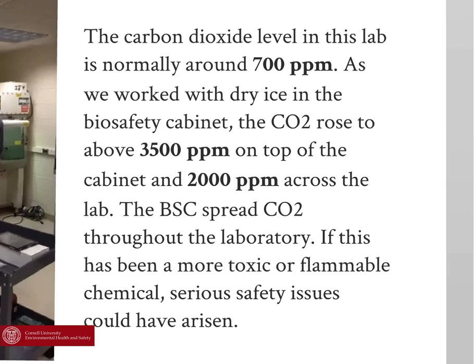The carbon dioxide level in this lab is normally around 700 parts per million. As we worked with dry ice in the biosafety cabinet, the CO2 level rose to about 3,500 parts per million on top of the cabinet and 2,000 parts per million across the lab. The biosafety cabinet spread CO2 throughout the laboratory. If this had been a more toxic or flammable chemical, serious safety issues could have arisen.